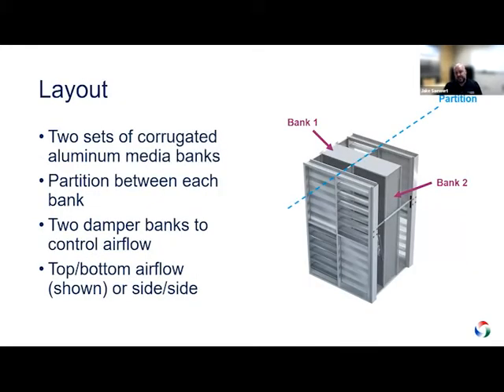The way these heat exchangers are laid out, as you see here, is you actually have two independent banks of the heat exchanger media. And in this case, we have a partition that's vertical. So you're not transferring air from left to right on this unit. The banks are independent. You also see that upstream and downstream, there's going to be two banks of dampers to control airflow. In this particular example, this would be suitable for an over-under energy recovery unit. So your top section could be outdoor air in this case, and then that would flow through the unit and come out the bottom as supply air.